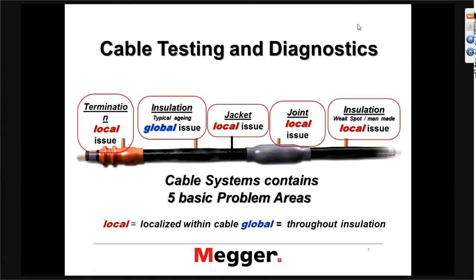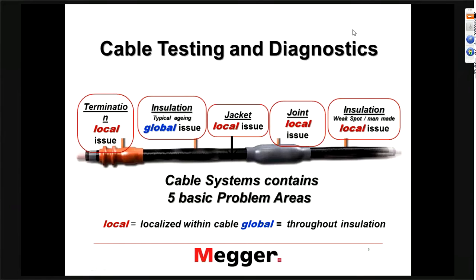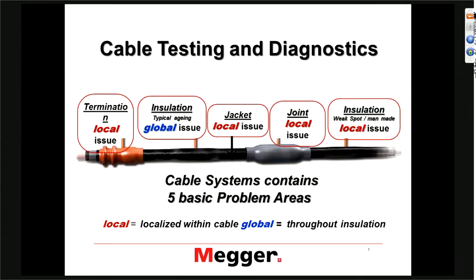We'd like to talk about partial discharge testing and Tan Delta testing and how they can be utilized in increasing reliability in cable networks. If we look at the first slide, looking at a piece of cable, there are five areas that are of concern. Starting from left to right, we see the terminations. Terminations can present a local issue in terms of cable reliability.